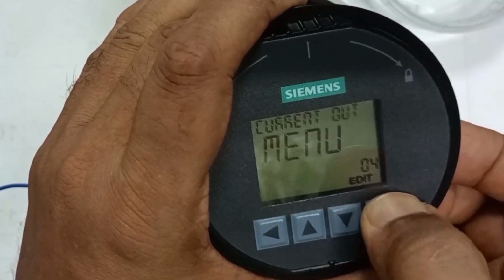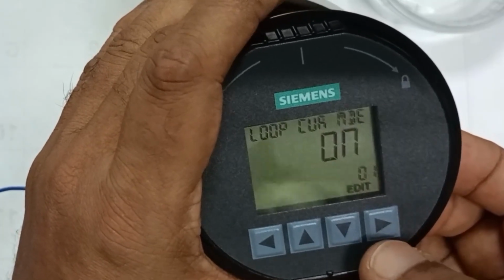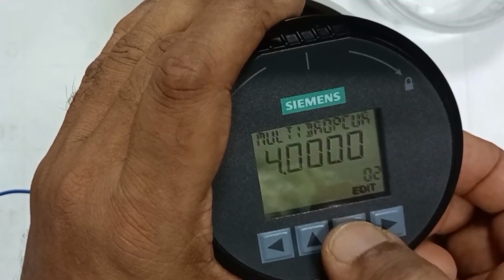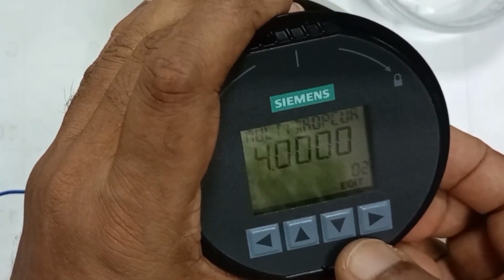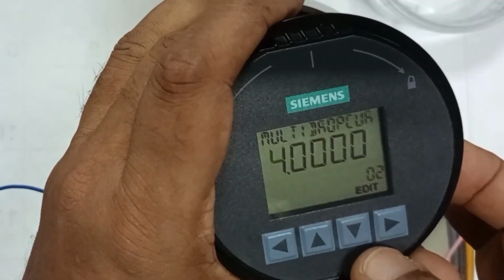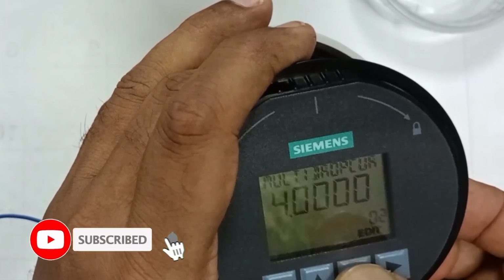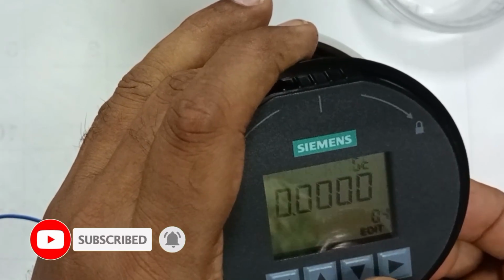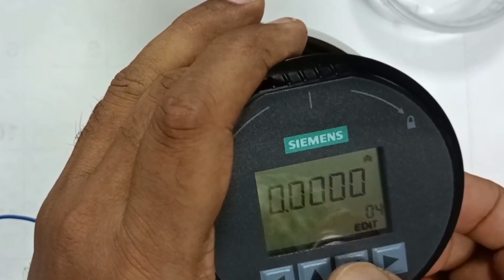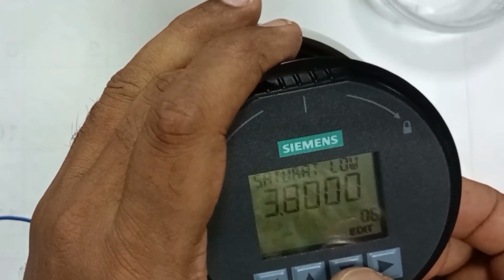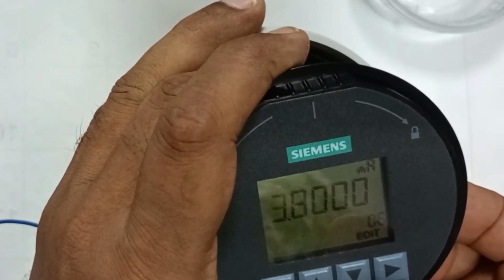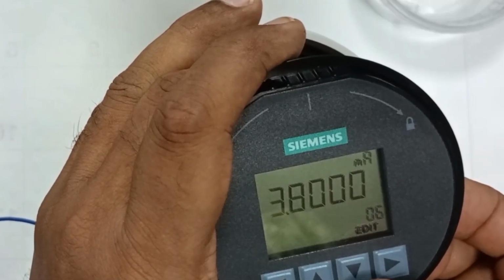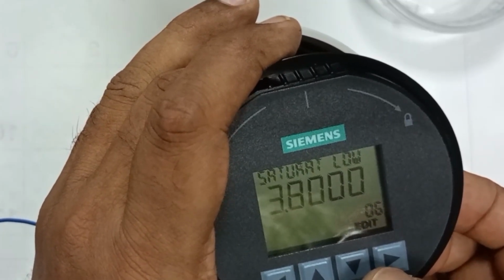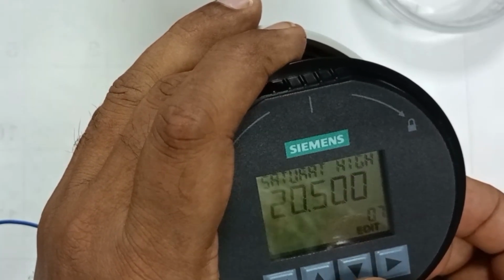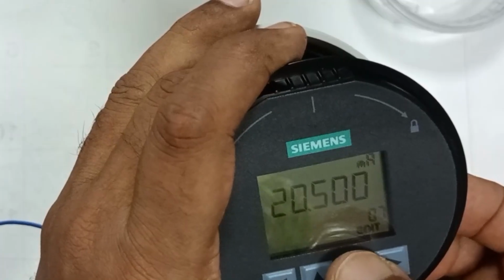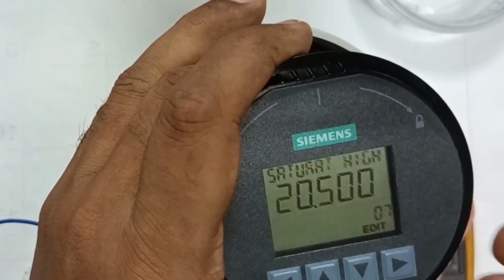Current output, here you see loop current. You can see multi-drop current, that means damping 0, lower range 0 meter, upper range 5. This is milliampere. Saturate low 3.8 milliampere, and this is saturate high 20.5 milliampere.